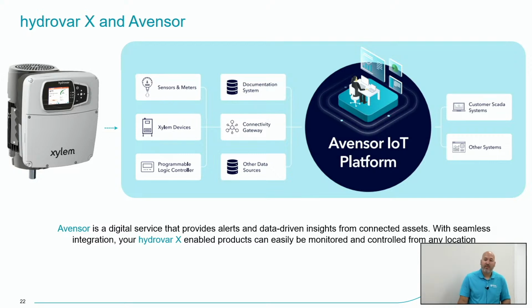This is almost basically like a BMS light system, so it not only can monitor our variable frequency drives, but really any piece of third-party equipment that has Modbus capability. You would just simply put in the points table into the application, and then you would be able to read or write whatever that specific product allows you to via its points table. However, if you're using one of our products, whether it's the Hydrovar X, IPC, they will be pre-programmed into the platform for you to simply say, I want to connect to this, and those point tables behind the scenes are automatically auto-populated for you, so you don't necessarily have to do that work.